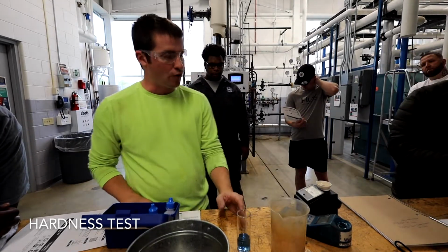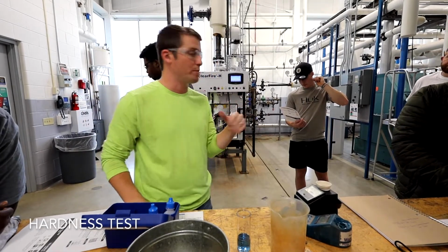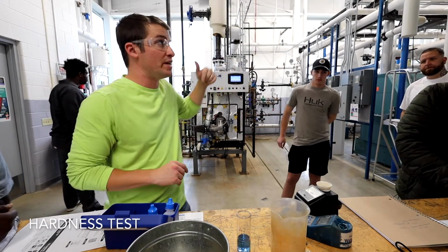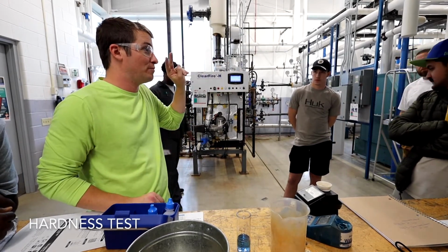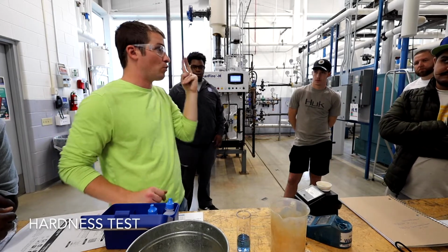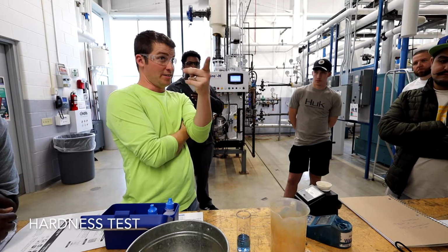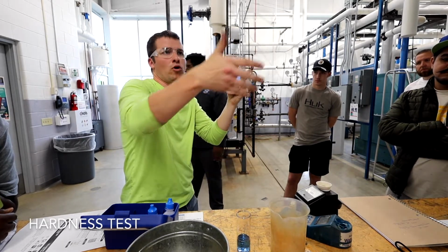We did hardness, 4.5. It would be red. Right, on my control range, I'd have 1 max and be saying that's too high. So that's gonna spin into why is it high? Where is the hardness coming from? It can only be 2 locations. Feed water tank. What feeds a feed water tank? Condensate is 1, or it'll be soft or RO, right?